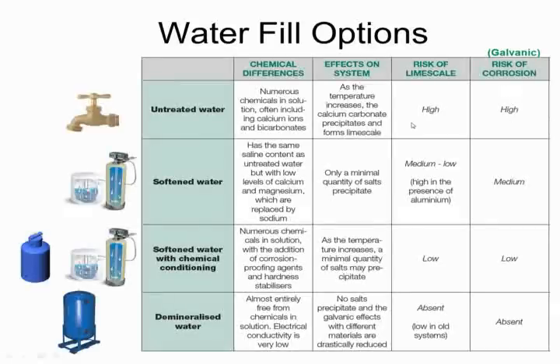And this quick matrix is a kind of a quick guide here. Starting at the top, if you have untreated mineral-laden water, your risk of limescale is going to be high and corrosion for galvanic attack high, as we showed. You can soften it. It will reduce, in some cases, even dramatically, your chances of limescale, but it doesn't too much improve your risk of corrosion. Now, after you fill the system after a softener, you can put chemicals in. Now you have taken your risk of limescale and corrosion down quite dramatically. The important thing is to make sure that you check the pH level and alkalinity of your system to make sure a year later and a year later and a year later that they're in the desirable range. And then lastly, and perhaps sometimes the most expensive way, is to demineralize the water, either through a distilling process or a demineralizer.